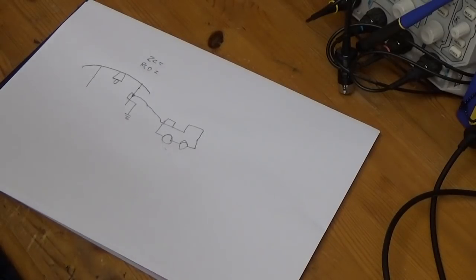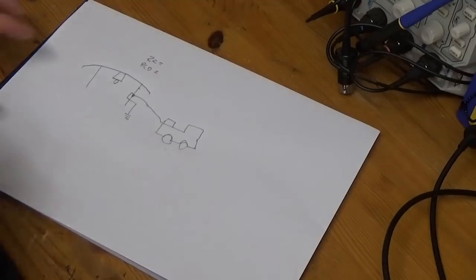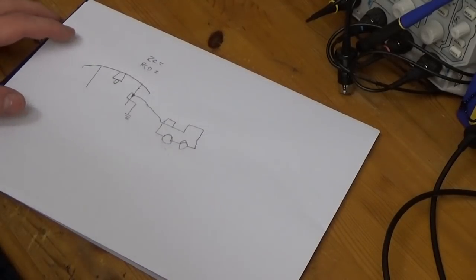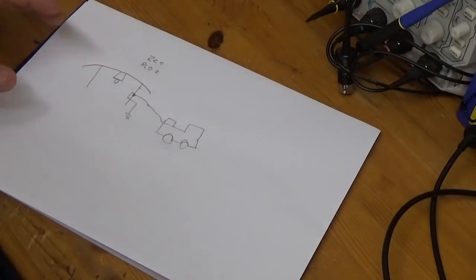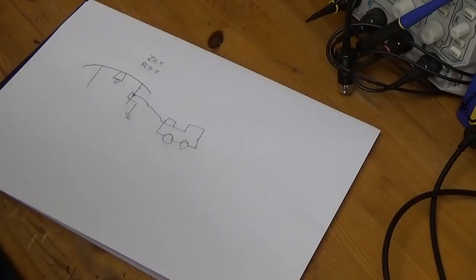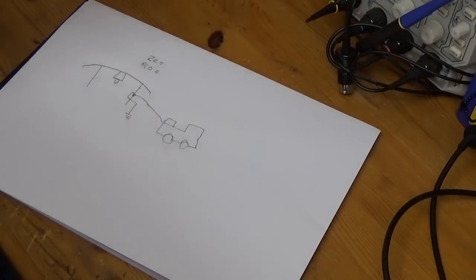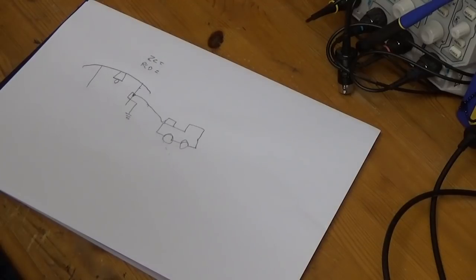So as you know, as you should know if you're an apprentice electrician at the moment, you need a loop in order for current to flow. That's why I call it a fault loop impedance. The problem is that generator is not referenced anywhere, is it? It's just floating. We referenced this side, but to what? The source is coming from the generator and we were just getting no fault loop impedance.